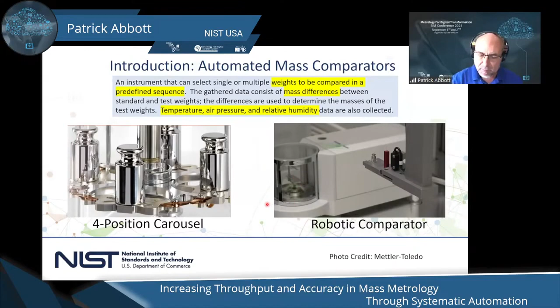On the left, we have a so-called 4-position carousel where 4 different weights can be loaded. The job of this carousel is to rotate a given mass over to the weighing pan of the comparator whenever it needs to be weighed. So that's great. It's all automated. It can be set up in advance, but it has a limitation of only 4 at a given time. That's in contrast to the other type of automatic comparator that we have, and that's a robotic comparator that uses a magazine that is filled with as many as 36 weights, and then a robotic arm to pick those weights up and to automatically place them on the mass comparator weighing pan. So that's what I mean about mass comparator.